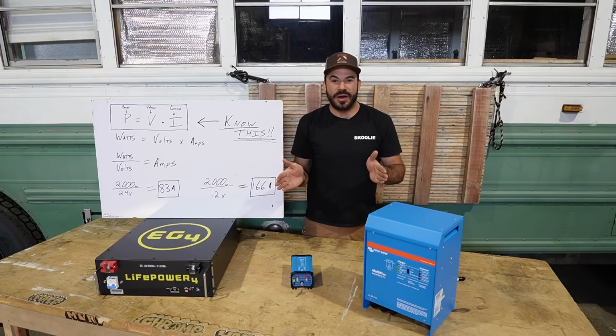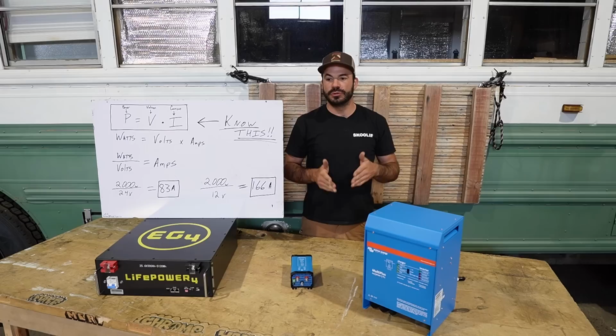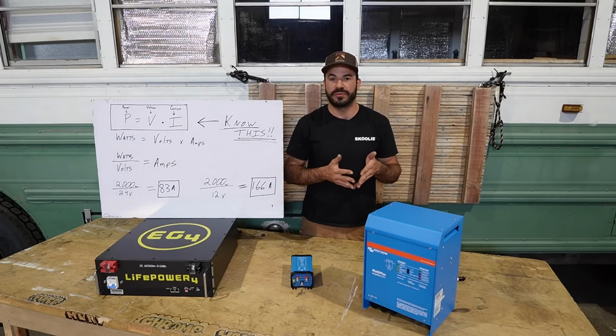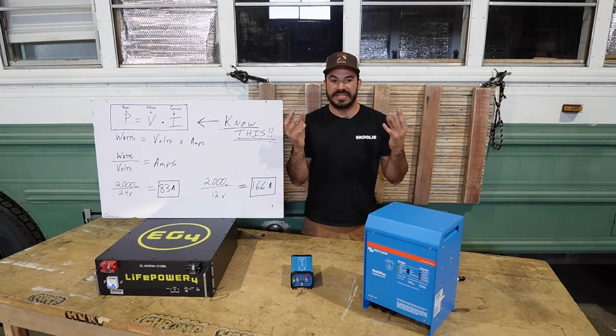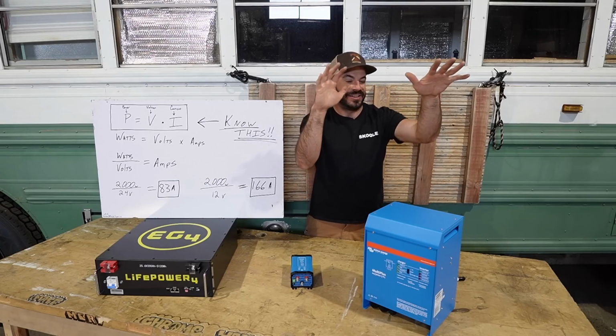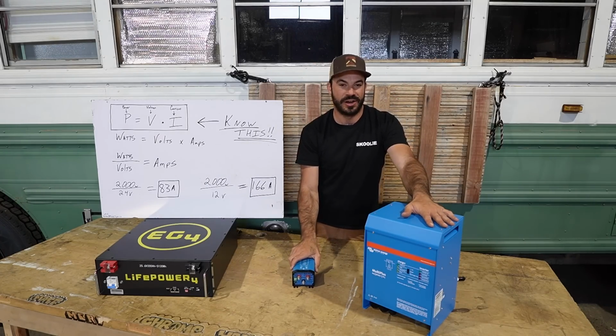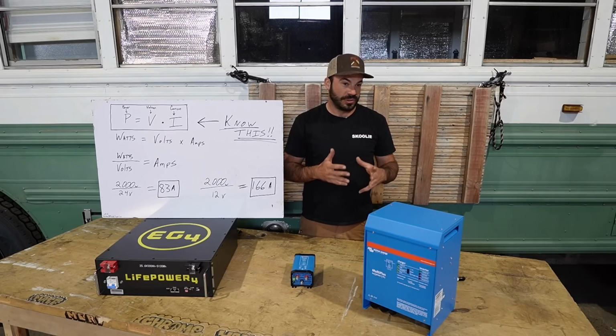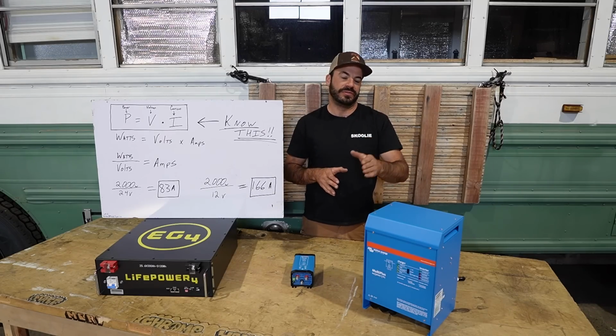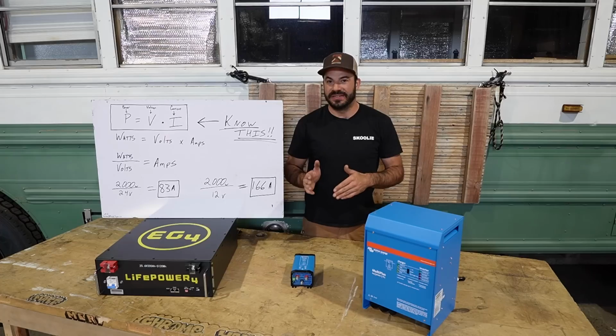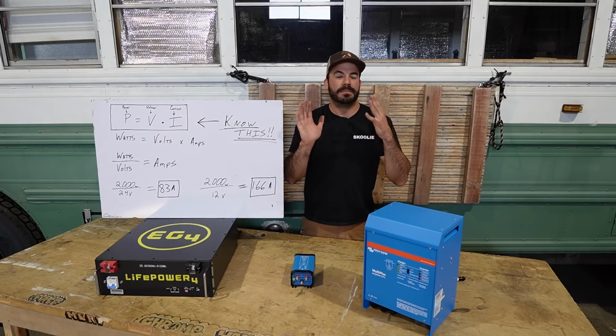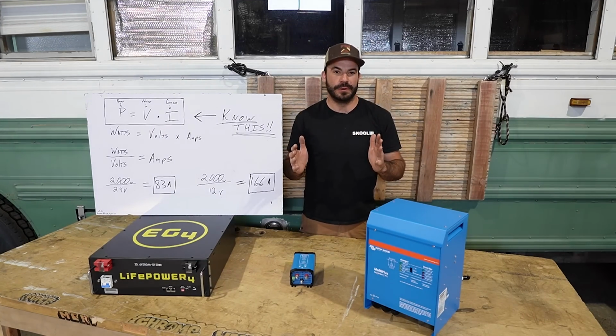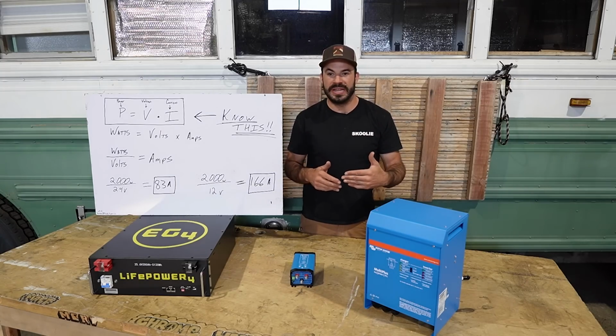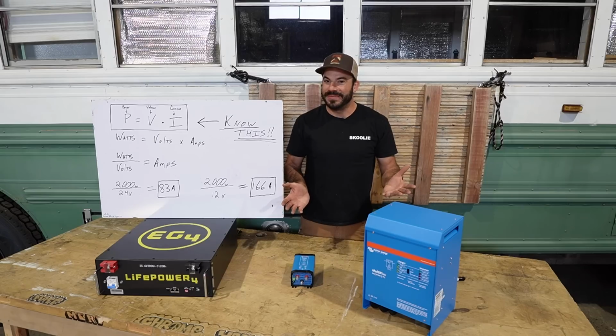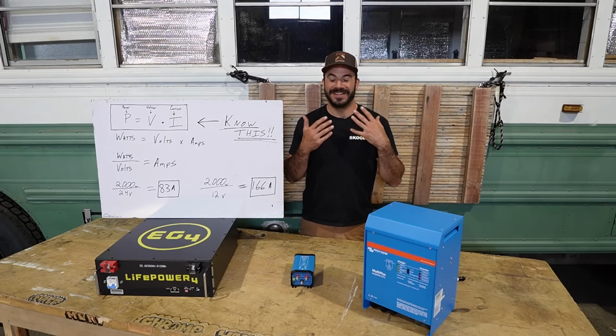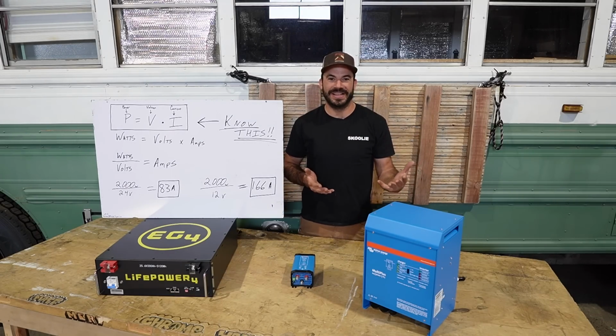If you lose one of 2, 3, or 4 24 volt batteries, your operating voltage is still going to be up in the parameters that your inverter and step-down converter want to see to stay on and running. That's why I really don't like wiring batteries in series to get to 24 volts, especially if they have a BMS inside of them, which all lithium batteries do, when you can just buy a 24 volt battery ready to go. If one of them goes down or you need to swap one, your system stays up. Uptime is critical when you're counting on this system to run your whole life and maybe even the way you make money on the road.